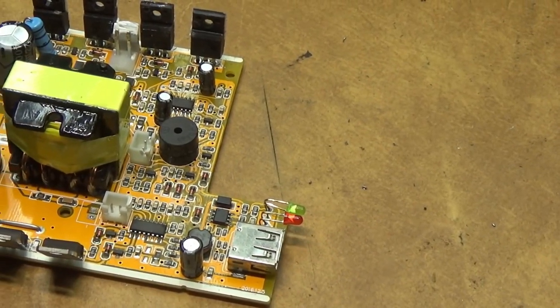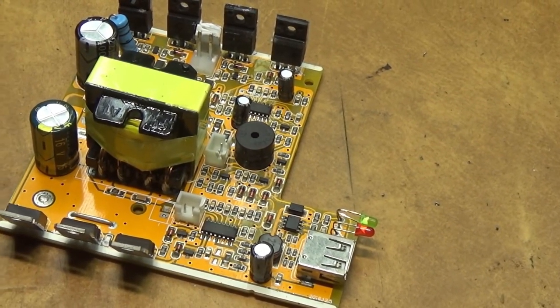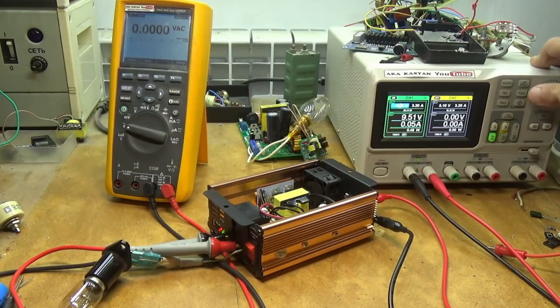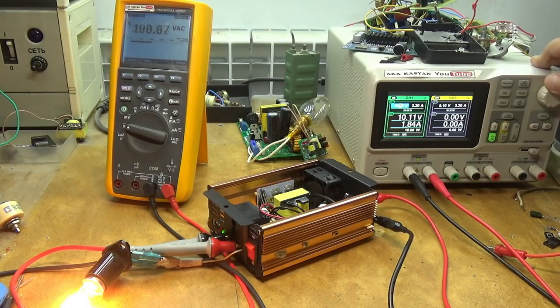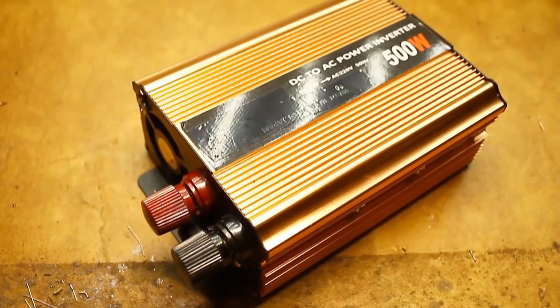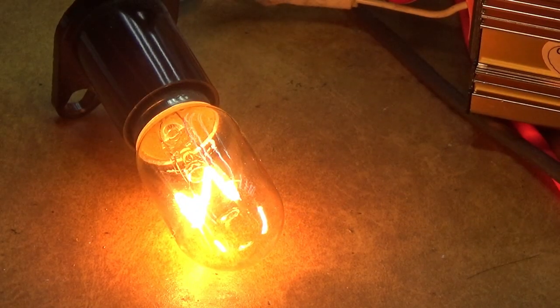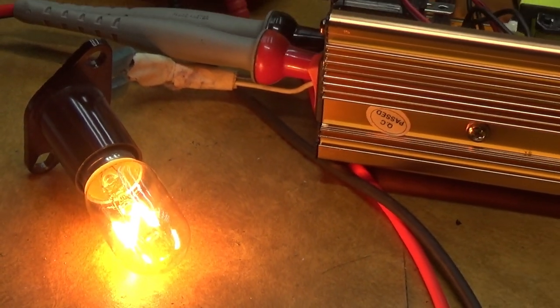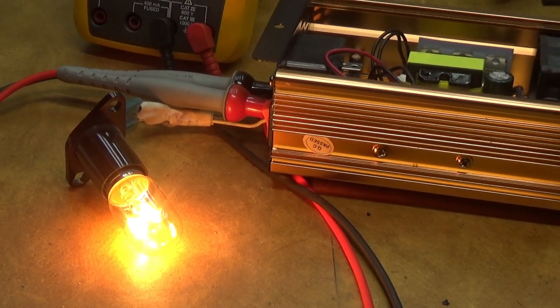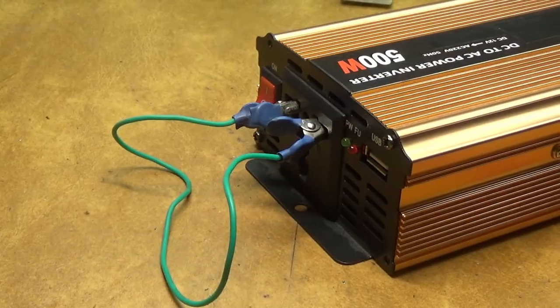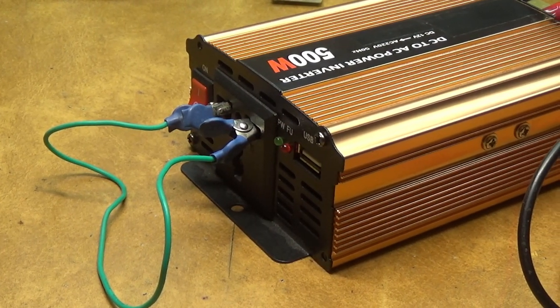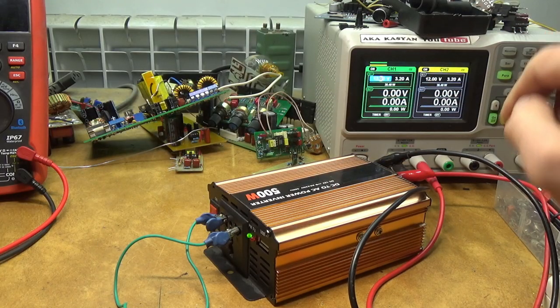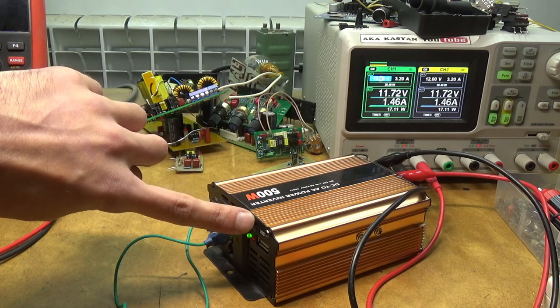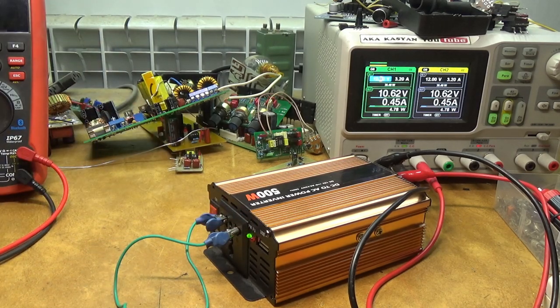It's important to note that the protection doesn't work according to the latch principle. If the voltage returns to normal, the inverter will restart itself. On the one hand, this is even a plus. You don't need to manually turn off and then turn on each time to remove it from protection. Let's short-circuit the inverter output to check the short circuit protection. As you can see, the protection works properly.